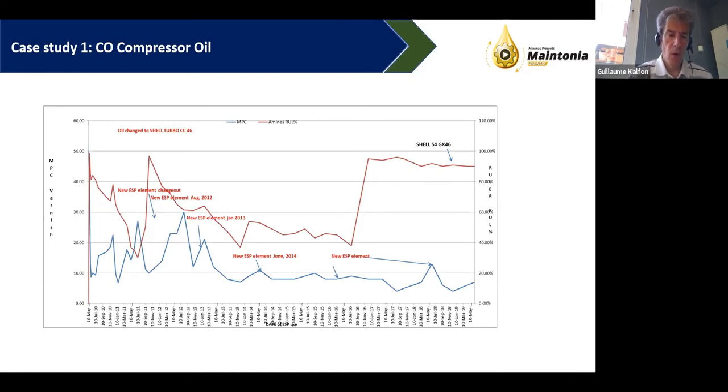And we see the same as I showed you before, a very fast drop in the initial phase, and then a bit of a bouncing tennis ball effect. It goes a few times up and down again as we are cleaning the full deposits in the full lubrication circulation system. And then in the end, we win. It's low, it's flat, it's stable, it's reliable.